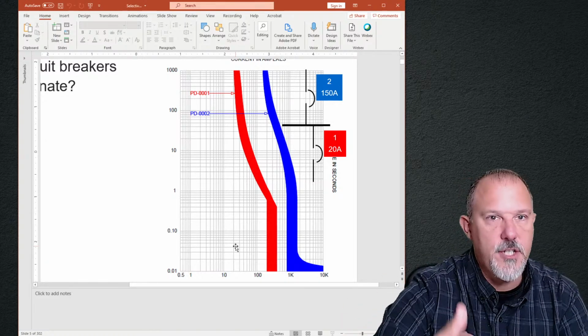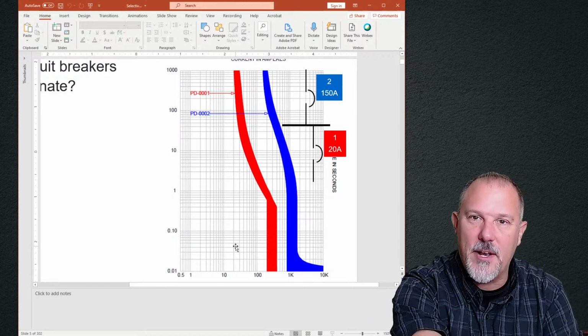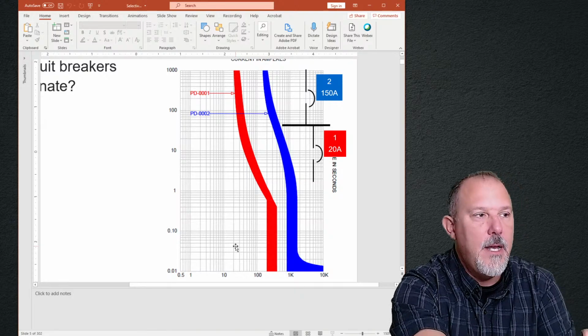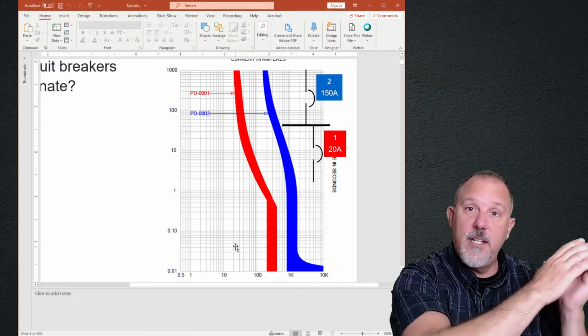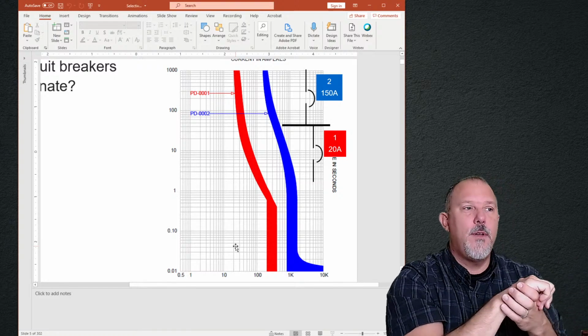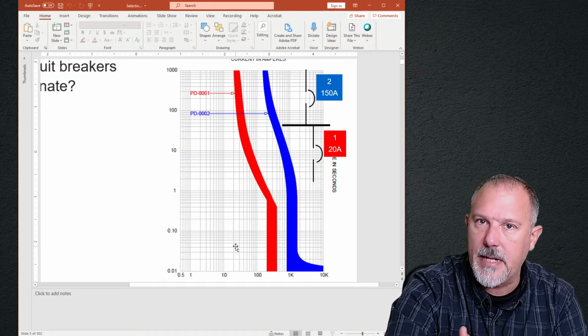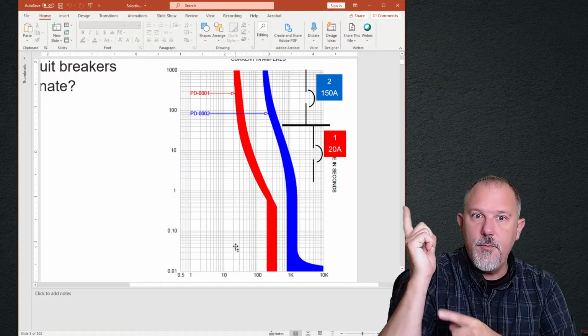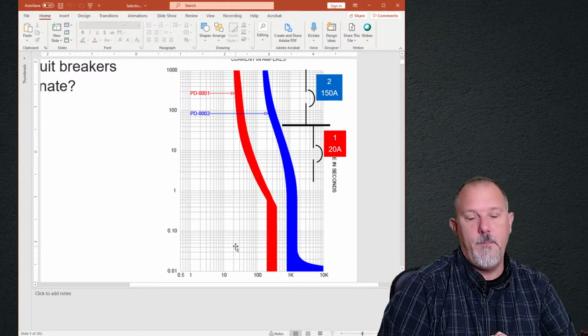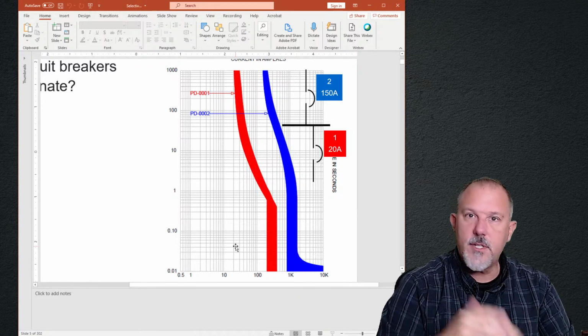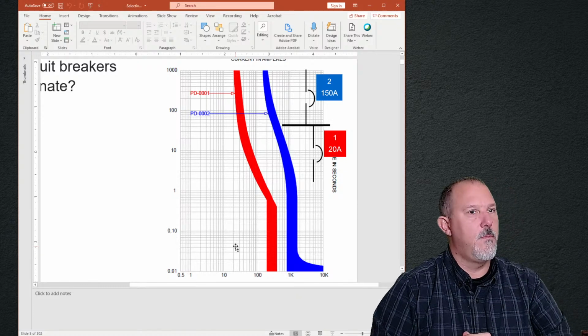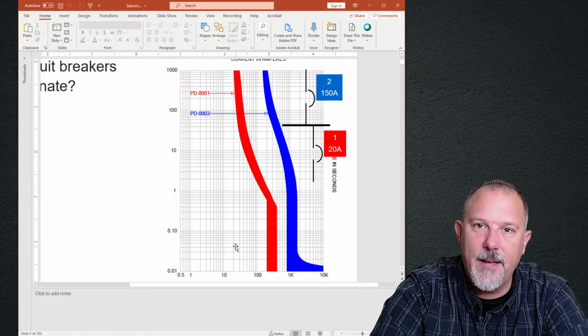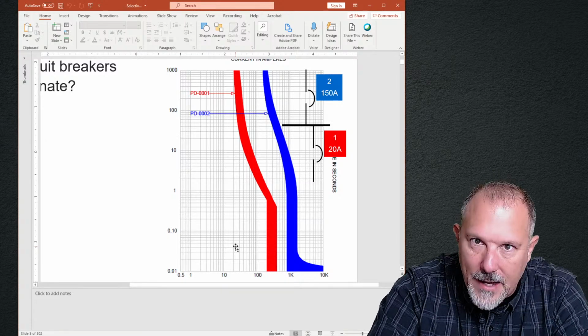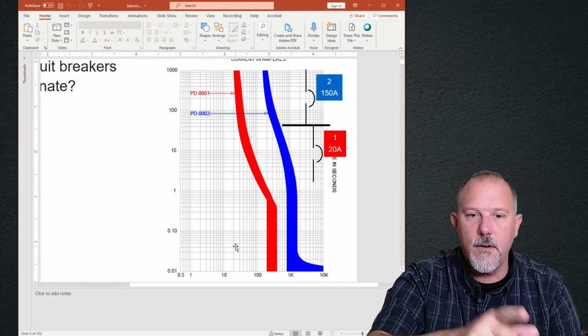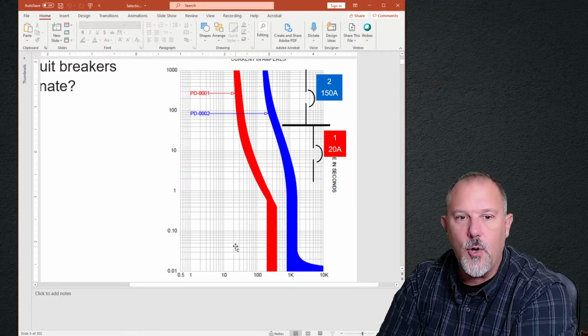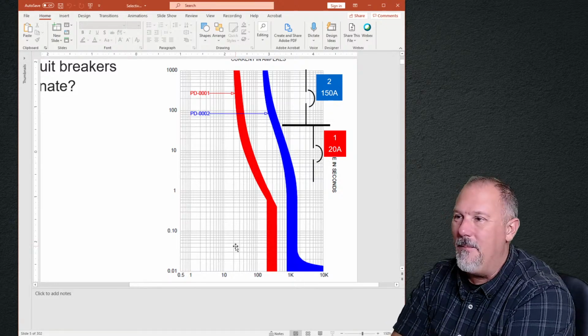So I was having a conversation with another really, really good engineer that I have a lot of respect for, technical wise. And I made the statement, I said, wow, you know, this individual who we both knew at the time, I was surprised, and I explained just what I'm explaining to all of you. And that person, I threw these curves up on, and I drew them on the whiteboard. And they said, well, those selectively coordinate. And I went, well, not for 10,000 amps of fault current or 5,000 amps of fault current. And they went, I have separation of curves all the way down to 0.01 seconds. Those selectively coordinate. And I'm like, no, they don't.